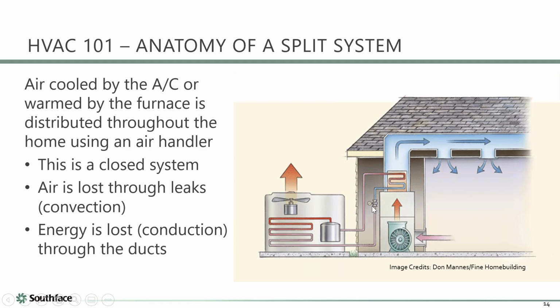And then what happens on the refrigerant side, it's basically a loop of refrigerant, and the refrigerant is constantly changing phase from a liquid to a vapor, and from a vapor to a liquid. I think we talked about this in the heat transfer one: if you have a pound of water at 210 degrees and you add 1 BTU of heat, it goes to 211 degrees. If you add 1 more BTU, it goes to 212 degrees. But after that, as you keep adding BTUs, it doesn't go to 213 degrees. It starts changing phase. In fact, to make all of that liquid water, 1 pound, about a water bottle's worth, change into vapor, it takes 1,000 BTUs. So it takes 1,000 BTUs to turn a pound of liquid water into a pound of steam. And likewise, when a pound of steam turns back into liquid, 1,000 BTUs are going along for the ride.